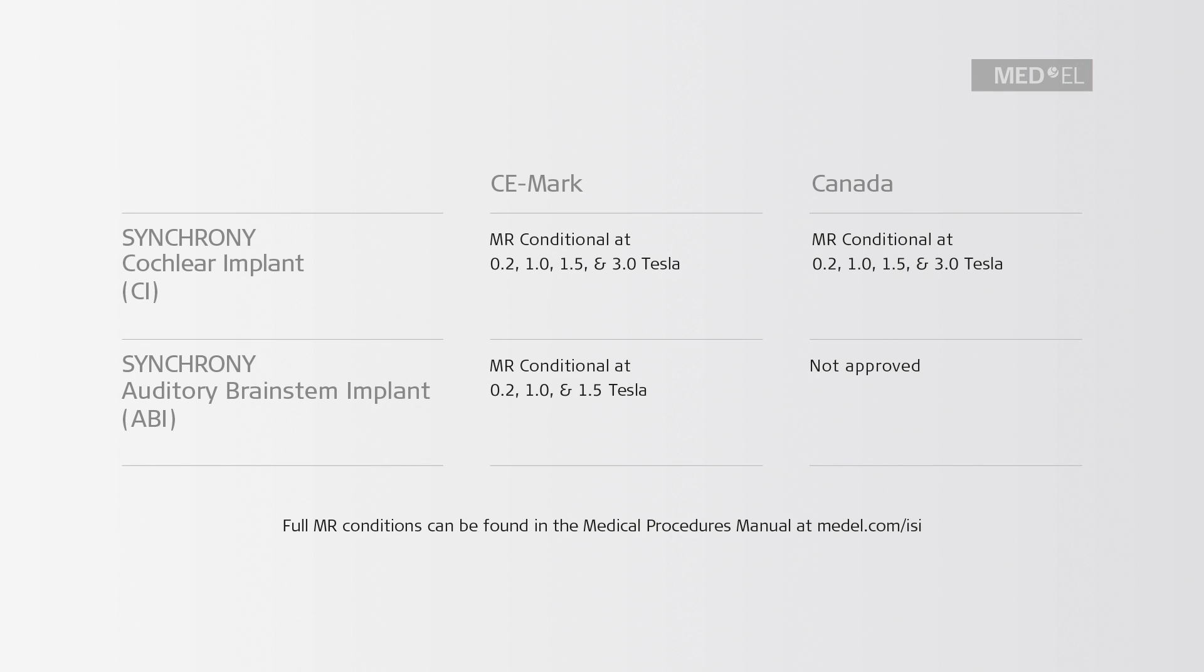when following the conditions detailed in the medical procedures manual. The synchrony auditory brainstem implant may be safely scanned at 0.2, 1, and 1.5 Tesla for countries accepting the CE mark, following the conditions detailed in the medical procedures manual, which is shipped with each implant. And you can always find an up-to-date version at medel.com/isi.